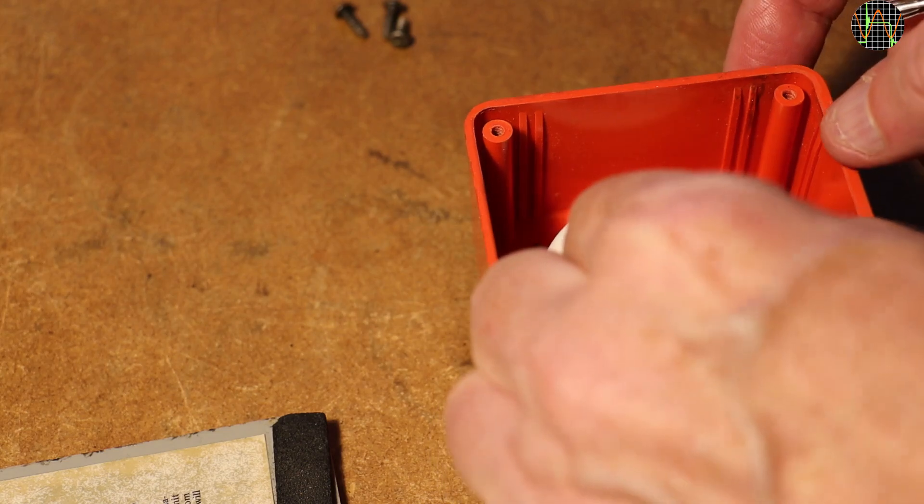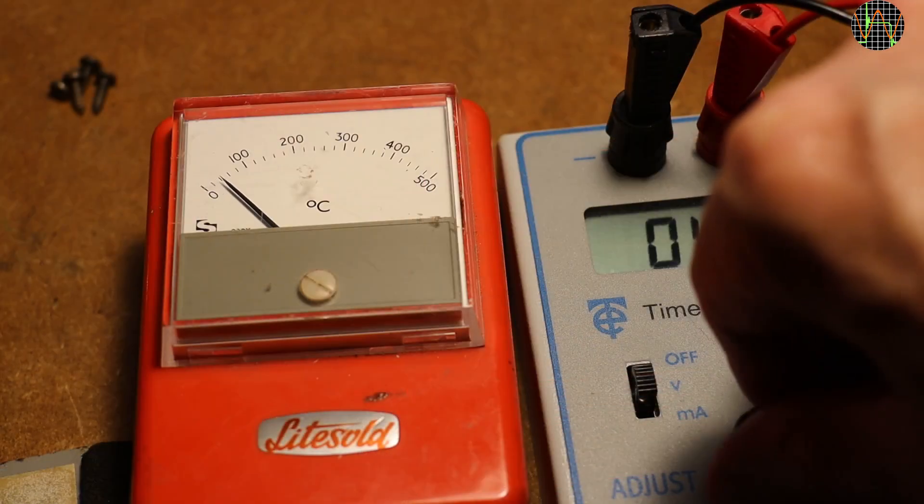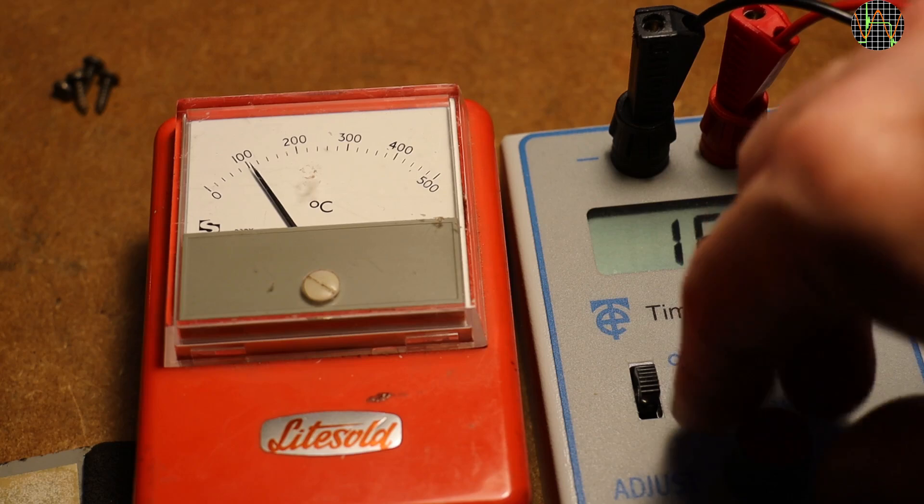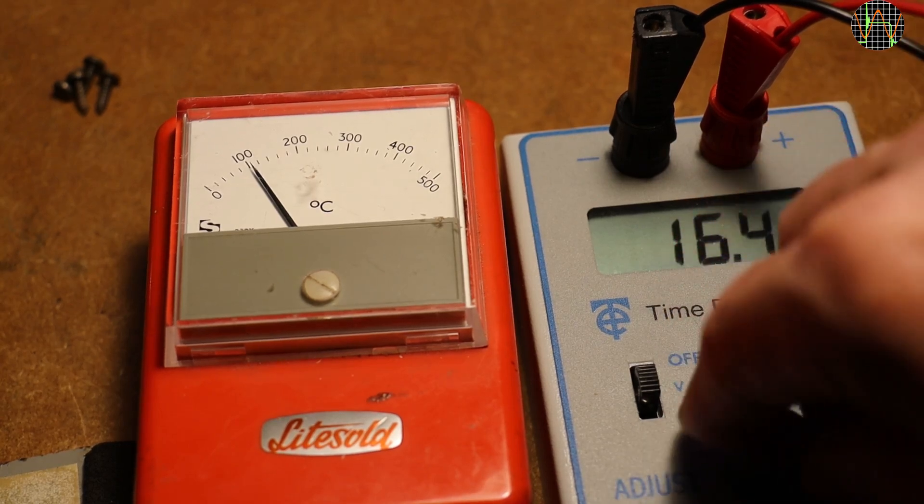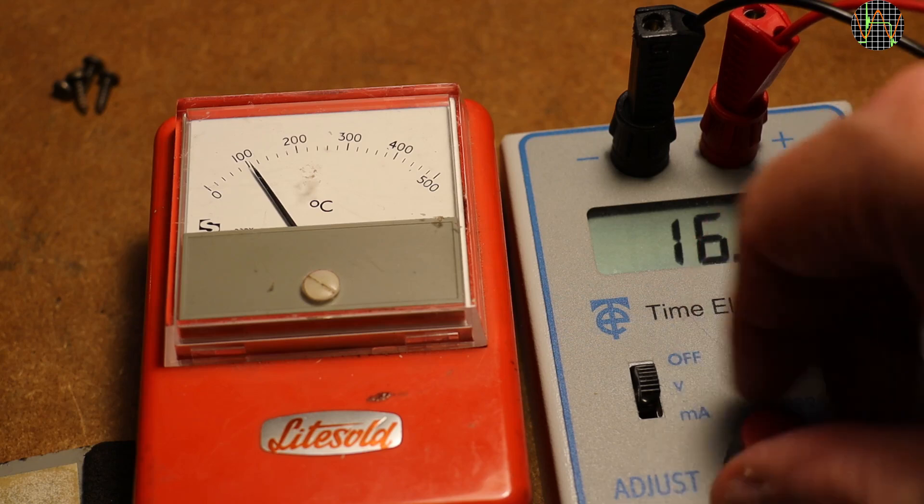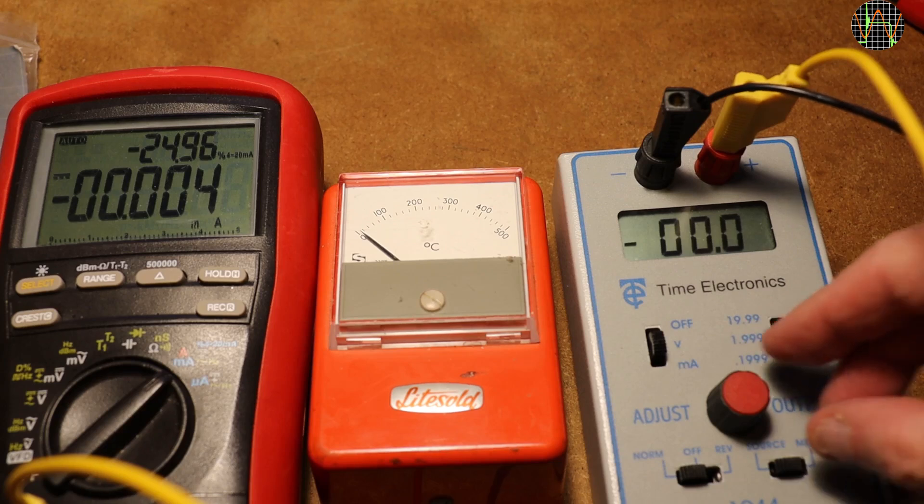Moving on, let's test the instrument by applying some test leads to it. I am using my calibrator in voltage mode, but something is wrong. The needle does not go over 100 and the calibrator is stuck at 16.4 mV. This is strange, obviously the instrument is drawing too much current for the calibrator to handle.